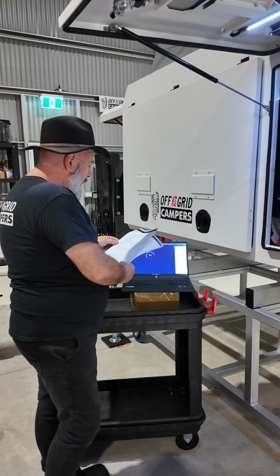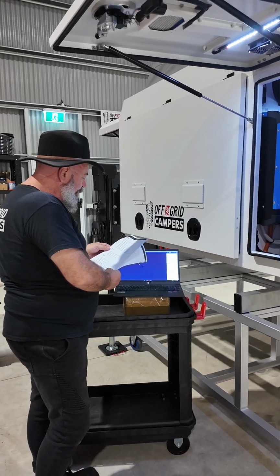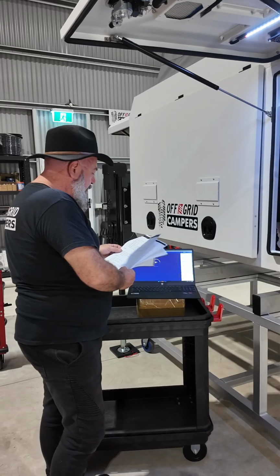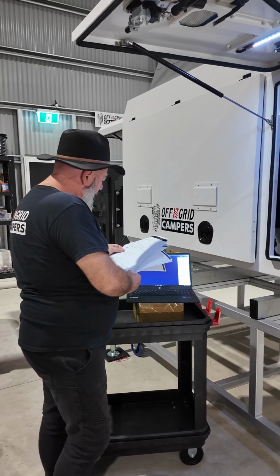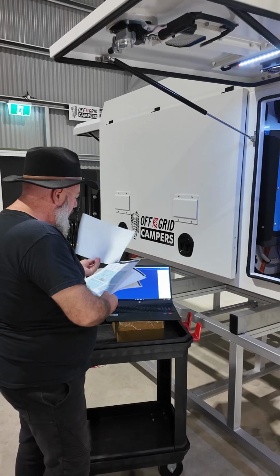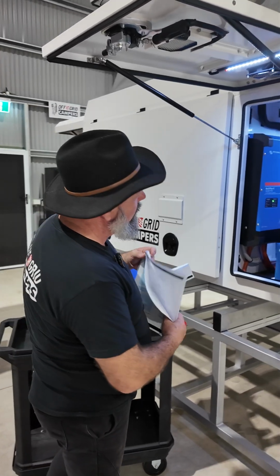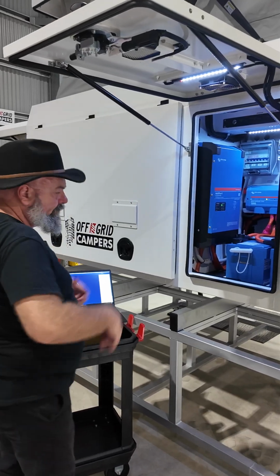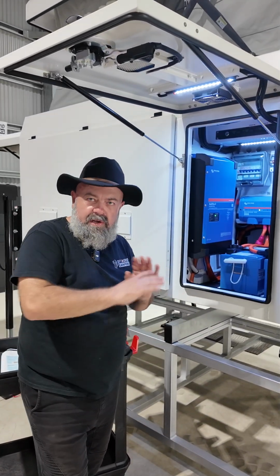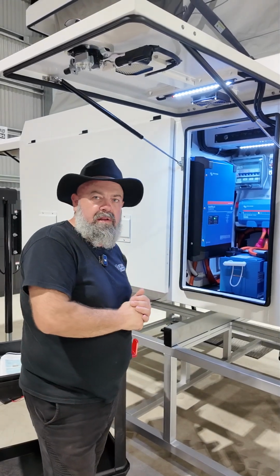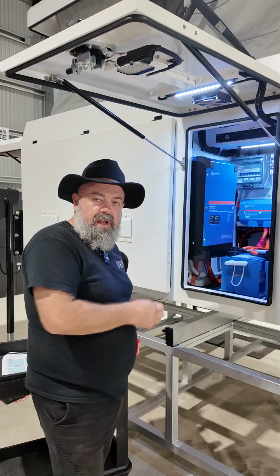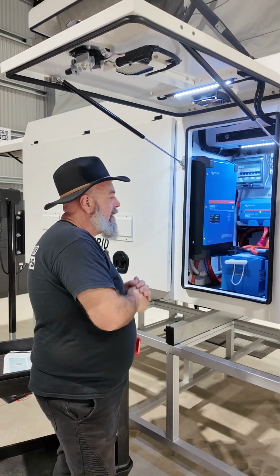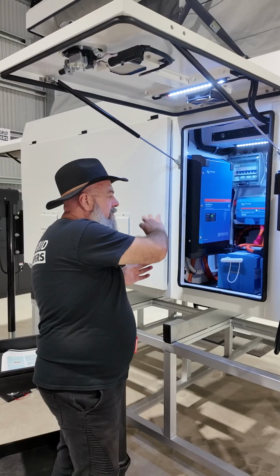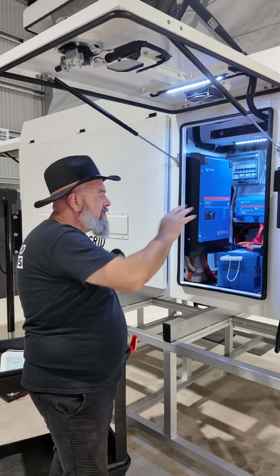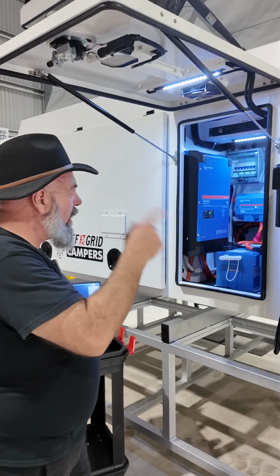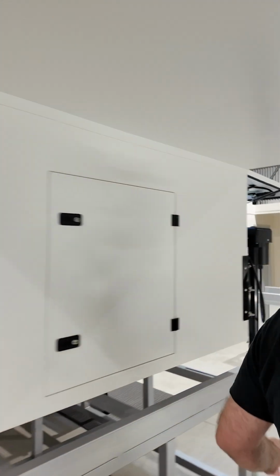Things like the discharge time, the tail current - things that don't mean much to a lot of people - all get programmed in with the inverter. For example, if the voltage is too low, it'll disconnect from the main supply if you're plugged in, and if the voltage is too high, it'll also disconnect, so we program that range in. Battery settings too - the inverter communicates with the batteries via the BMS. The whole system's integrated, so we'll go around the other side and show you the receiving end of it.